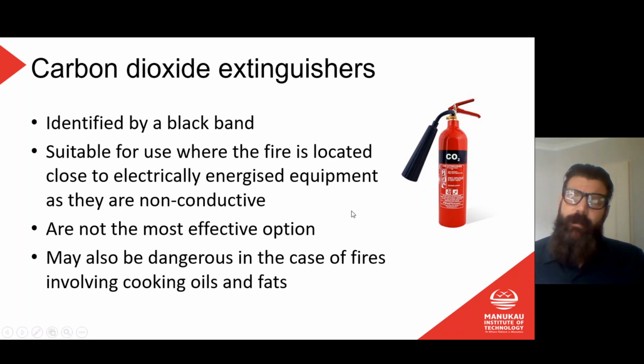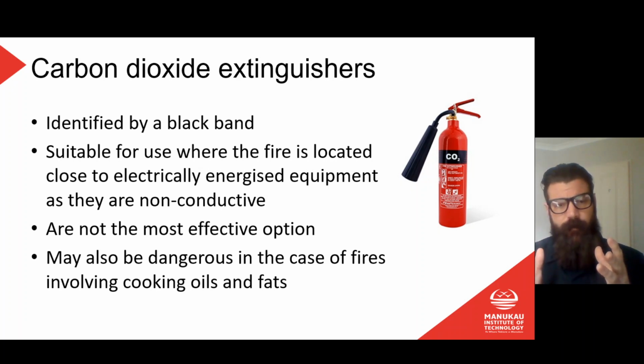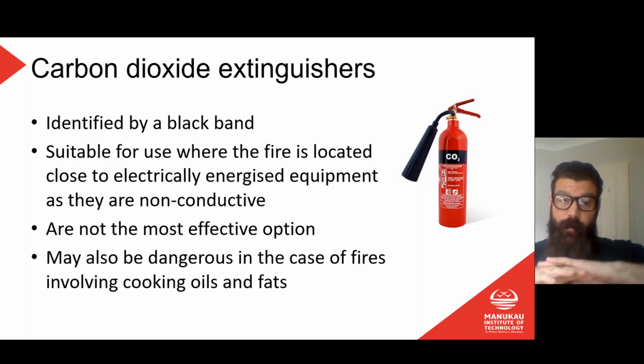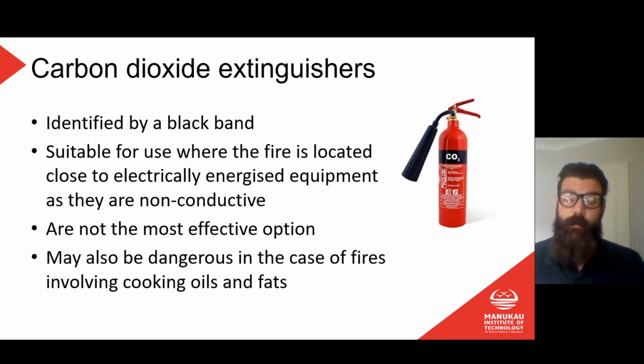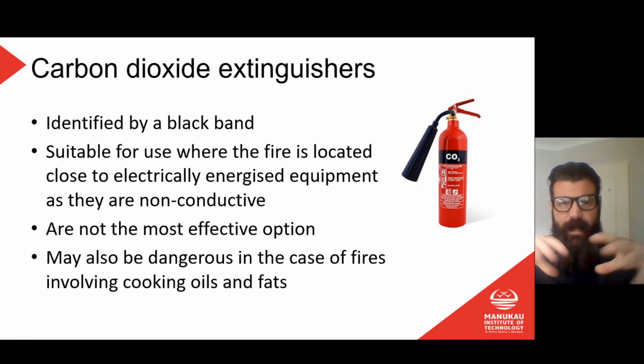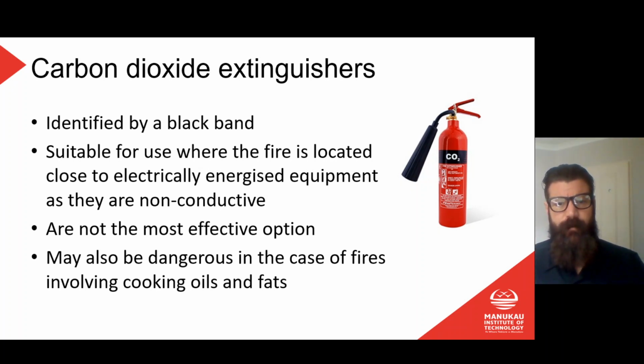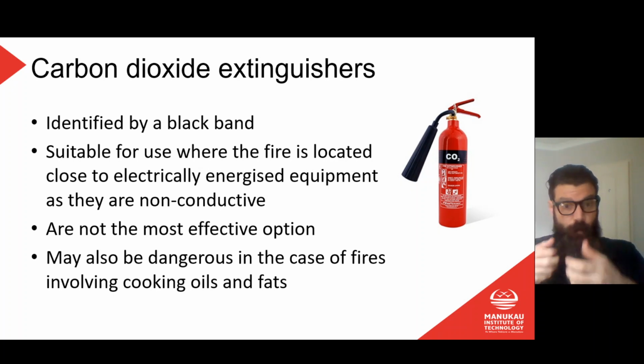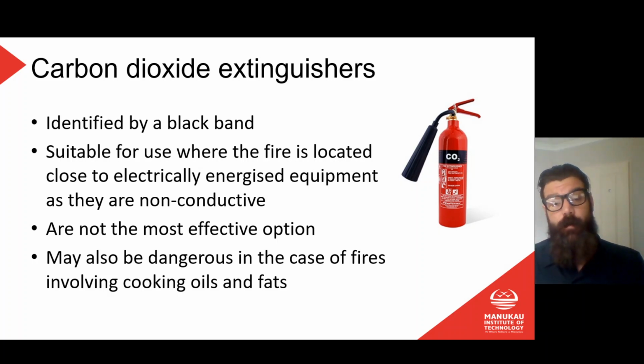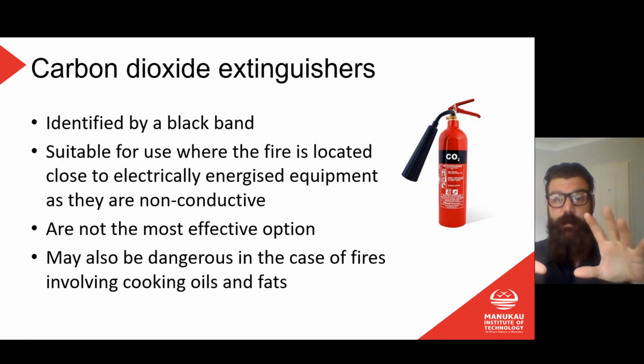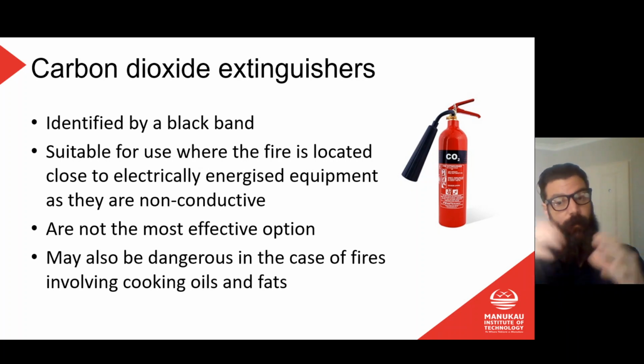Okay. So some of the issues there, it's not the most effective option, as it says here. That's because if you think about it, when we fire, say, dry powder onto a fire, like I said, it creates a layer of powder on top of the fire and thereby reduces the ability for that fire to get oxygen. If you talk about carbon dioxide, there's no way to make that carbon dioxide stay where you have sprayed it. It's a gas, it's going to go everywhere. While you're spraying the CO2 onto the fire, that continuous stream of CO2 across it is going to stop any oxygen from getting in there. And hopefully the idea there is that it puts the fire out pretty fast.